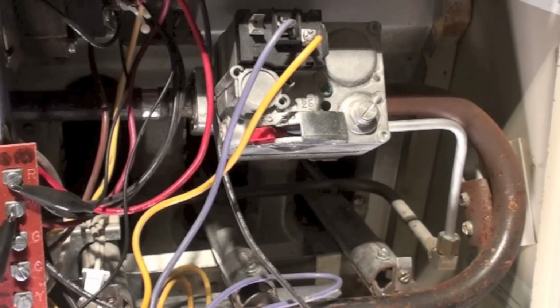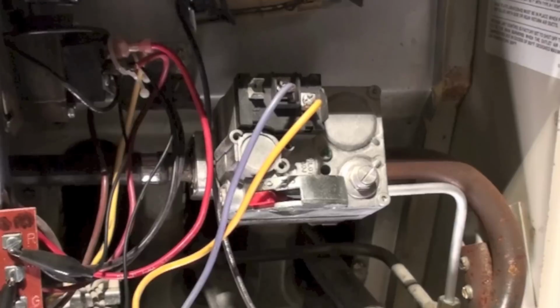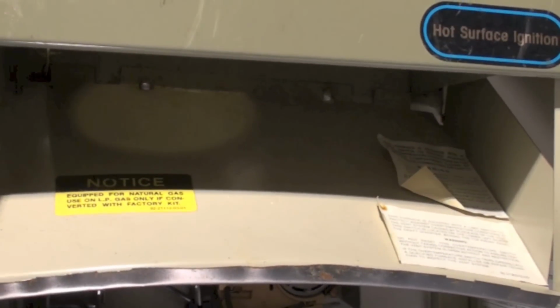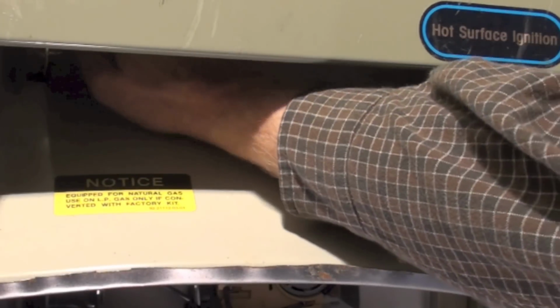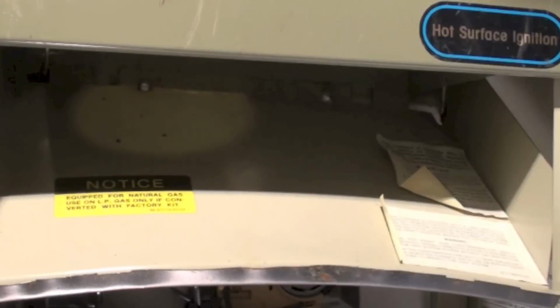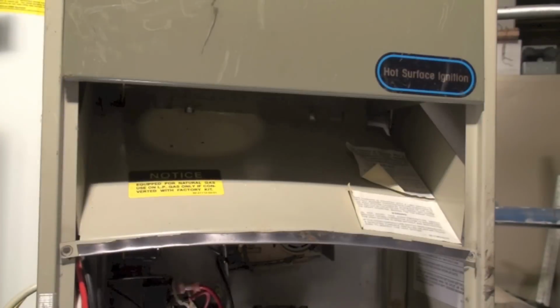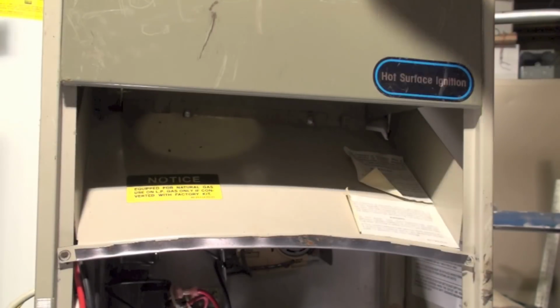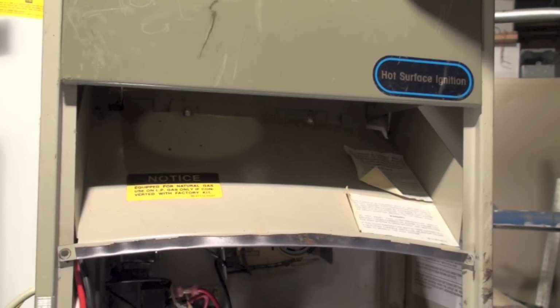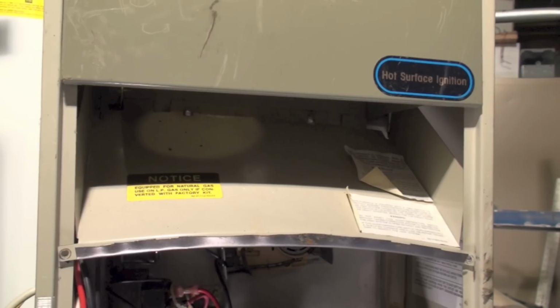Okay, I've eliminated the thermostat, I've eliminated low voltage, but nothing still seems to want to happen. Nothing's going on. There's one little thing on this particular furnace, and a number of other furnaces had the same thing. It's called a draft spillage switch. There's the draft hood. The gases are coming out. Inside here, there are heat exchanger tubes, and they're supposed to go straight up here and come out of the vent pipe here. So if they spill out of here, that means the vent's plugged. And there's a switch in here, just a little heat-operated switch to shut it off. I'm going to show you where it's at. Now, they're not all in the same place, but on this Rheem, they all are.